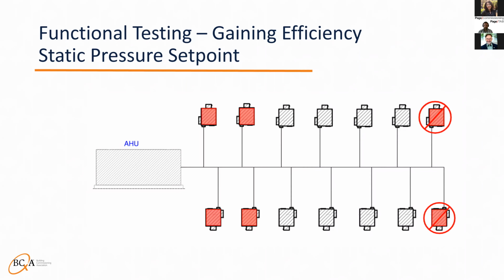Command all boxes to full cooling, but then start commanding the boxes closest to the unit to minimum flow or heating mode until the box total adds up to the AHU total. I don't like to shut dampers because I always want all my boxes controlling and modulating during the step so I can see if there are any PID loop issues. Do not command the boxes furthest away from the AHU to minimum because they are likely to be your worst case dampers. I have them marked out in the picture.